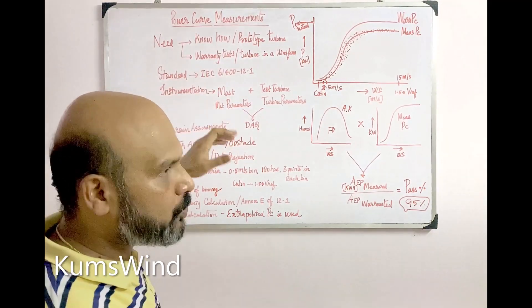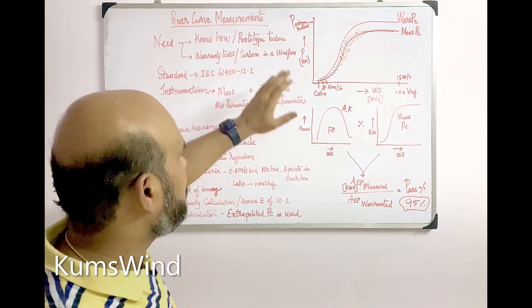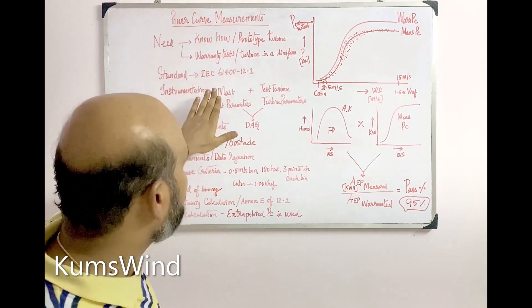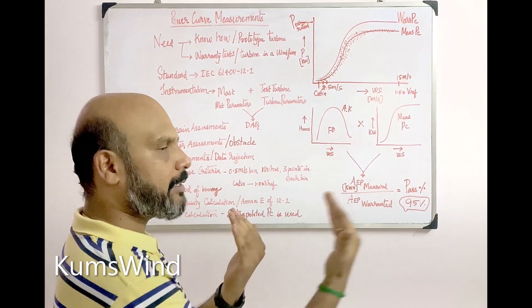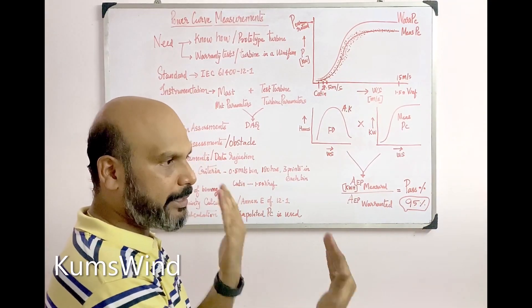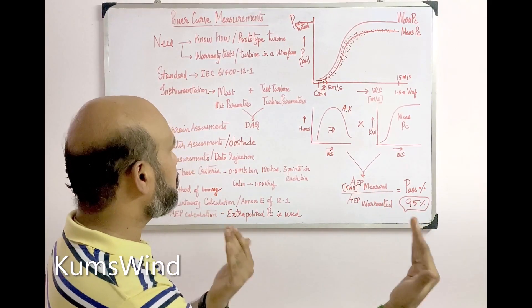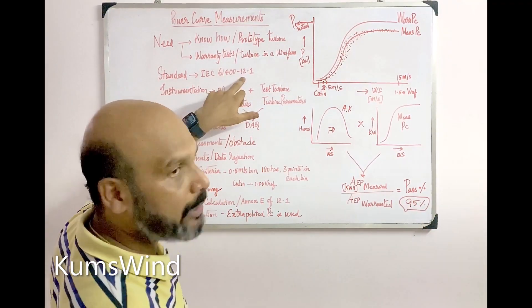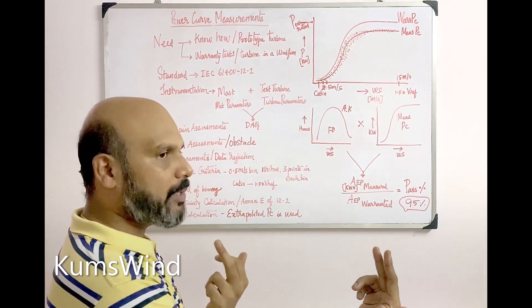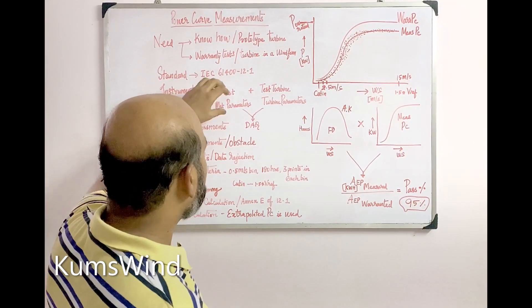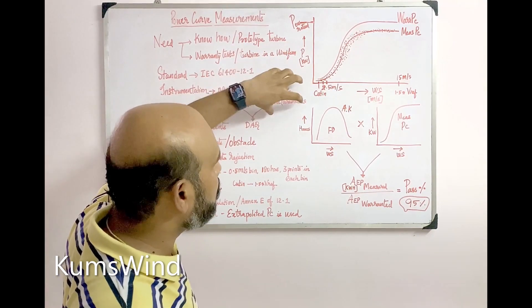The instrumentation setup needed for power curve measurement includes a meteorological mast placed exactly in front of the test turbine at a distance of 2 to 4 times the rotor diameter. This distance is governed by the IEC 12-1 standard, which states the ideal distance between the test turbine and the mast is between 2D to 4D. A meteorological mast is erected in front of the test turbine.